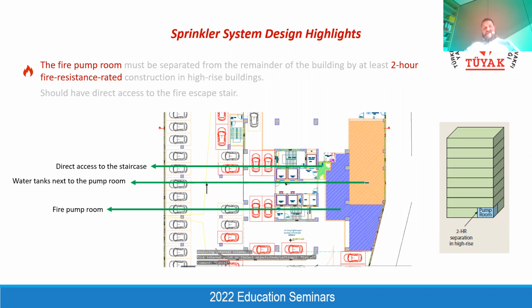And the only way to access the fire pump room without affecting the fire incident within the building is to have a direct connection between the fire pump room and the staircase. That's why we are always checking at the beginning of the project whether we have a direct connection to the staircase without passing other areas such as car parks or any other office area or residential area. This is also important. At the first stage of the project, you need to decide the location of the water tanks, and just next to the water tanks, there should be a fire pump room, which is directly connected to the staircase. And then you give this location to the MEP designer, the mechanical designer, and they check whether the fire pump room area is adequate to put the fire pumps in.